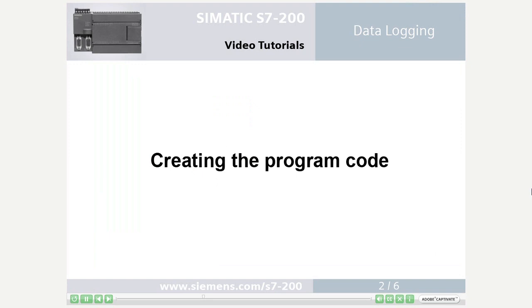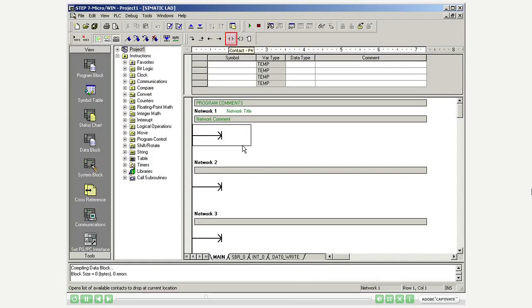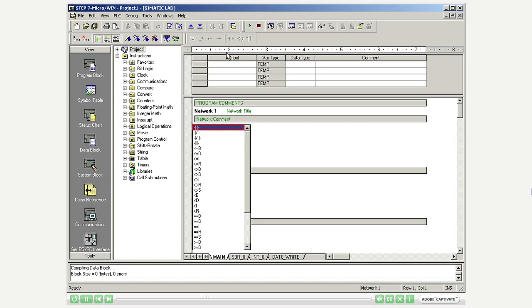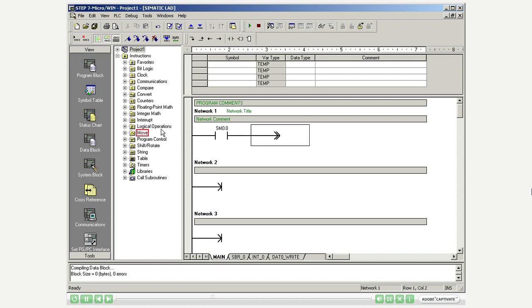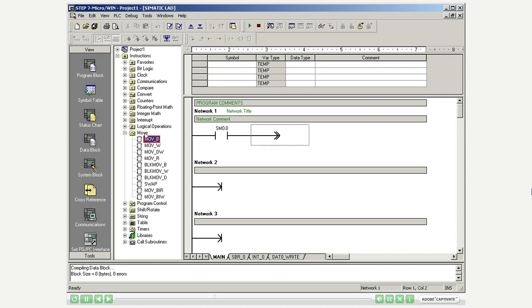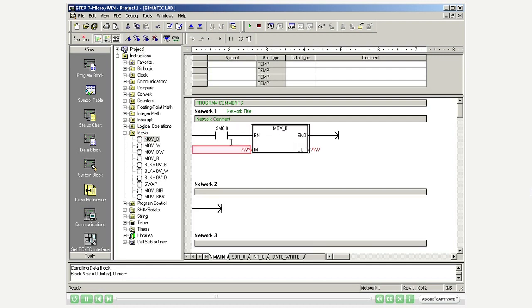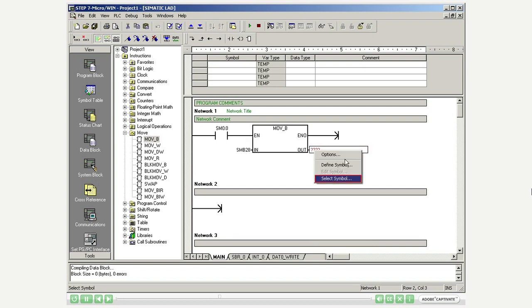Step 2: Creating the program code. Programming the operation block, Network 1. Transfer the dedicated special memory bytes of the analog potentiometers on every program scan to the addresses selected in the Data Log wizard. Define these addresses by right-clicking and selecting the symbol.